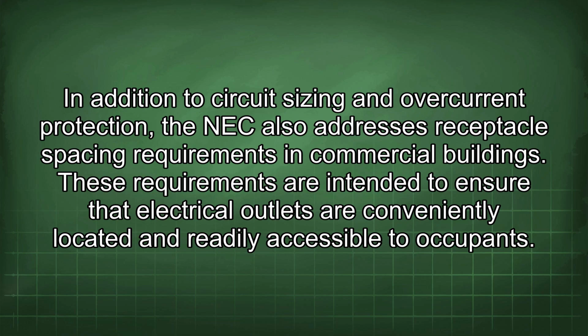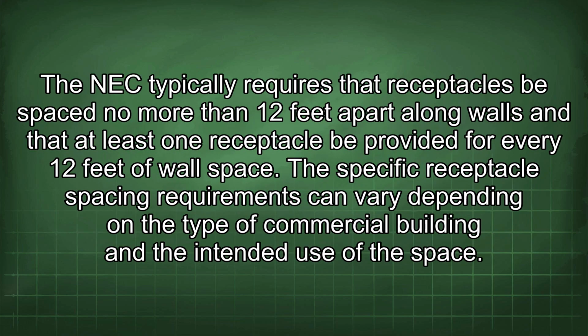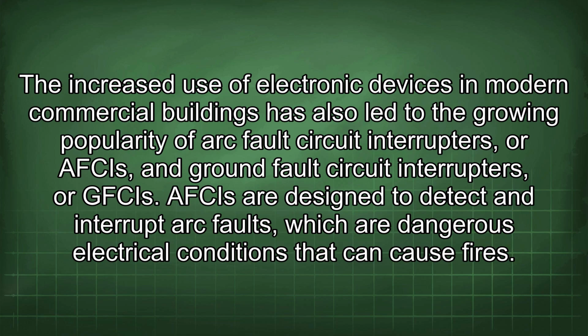These requirements are intended to ensure that electrical outlets are conveniently located and readily accessible to occupants. The NEC typically requires that receptacles be spaced no more than 12 feet apart along walls and that at least one receptacle be provided for every 12 feet of wall space. The specific receptacle spacing requirements can vary depending on the type of commercial building and the intended use of the space.